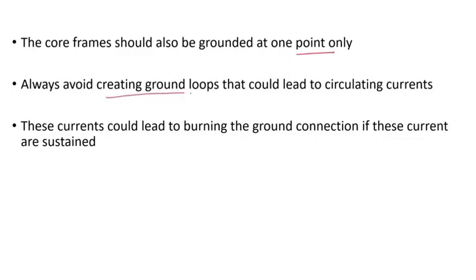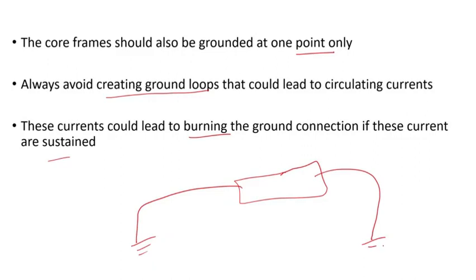Always avoid creating ground loops. That's why you don't want more than one ground, because if you have more than one ground, now you've created a loop, and current can circulate in that loop and cause heating and other things. These currents could lead to burning the ground connection if they are sustained. In other words, if you have the frame, let's say the top, and you ground it at this point, someone might think, well, if I have two grounds, I have redundancy. For instance, if one of them comes loose or fails, I still have another one.